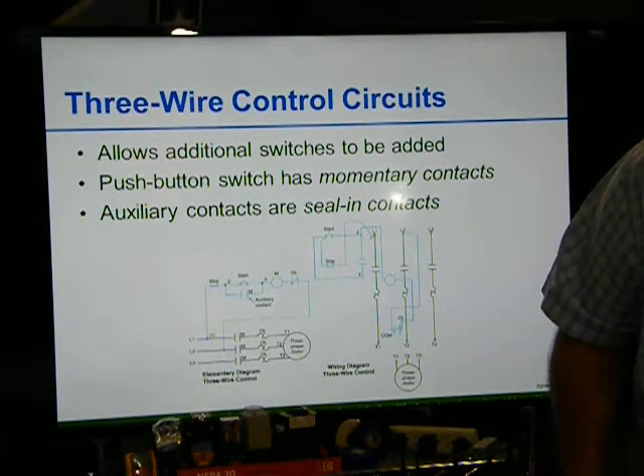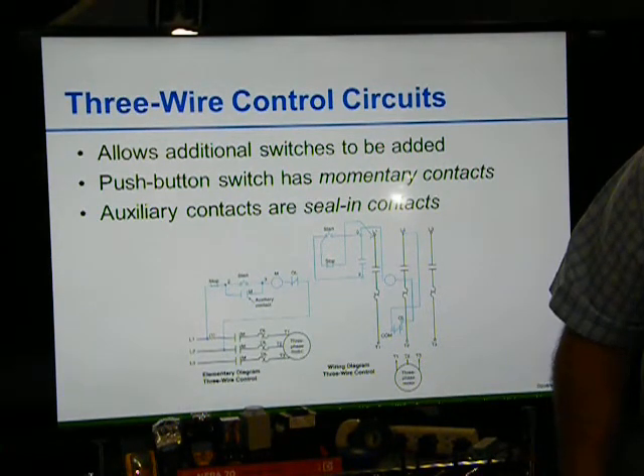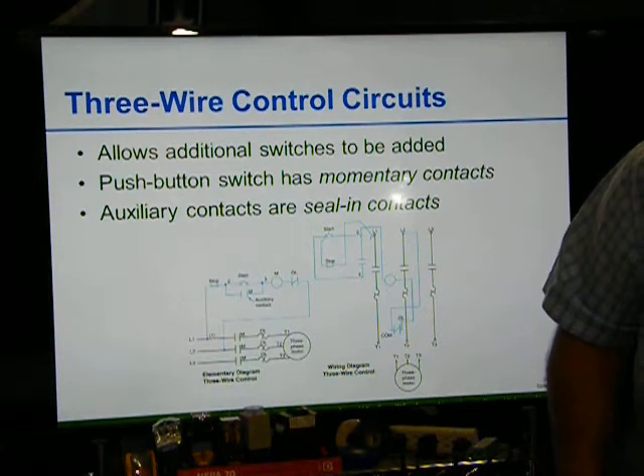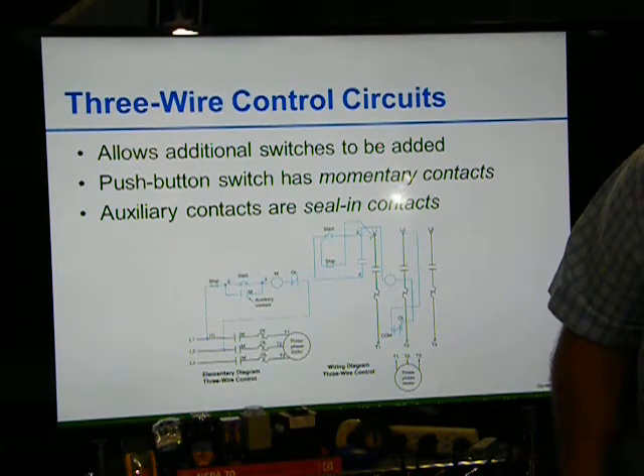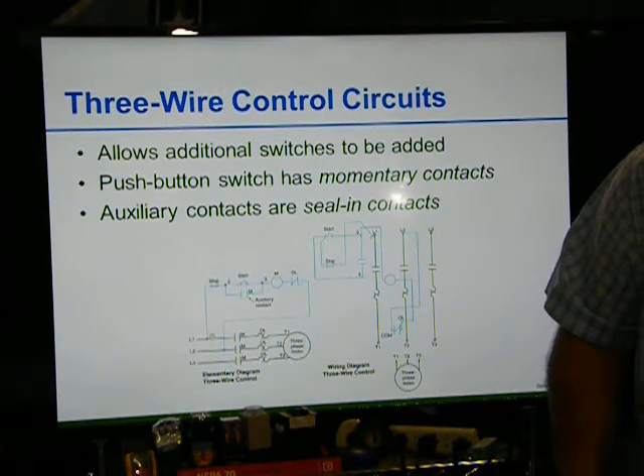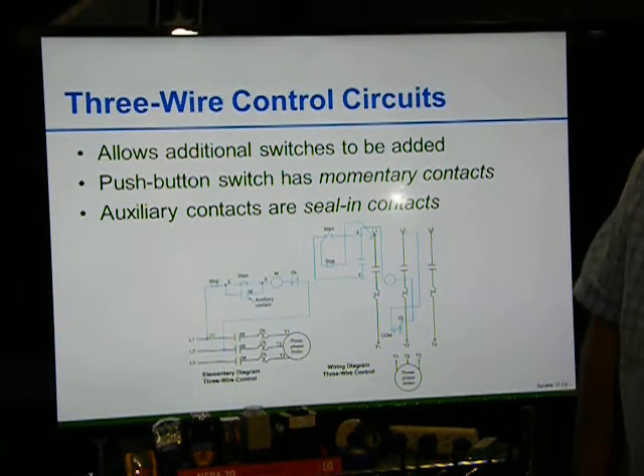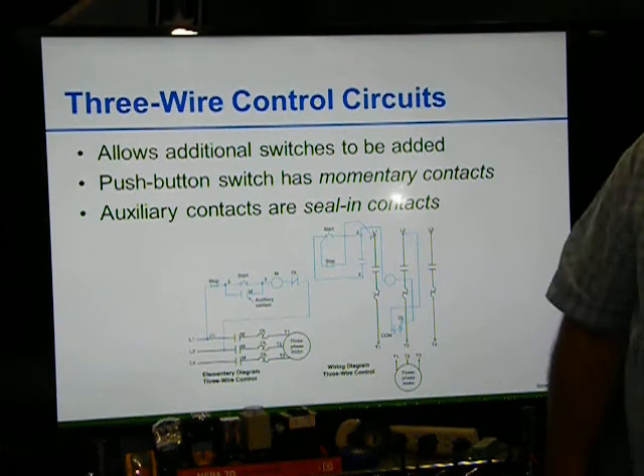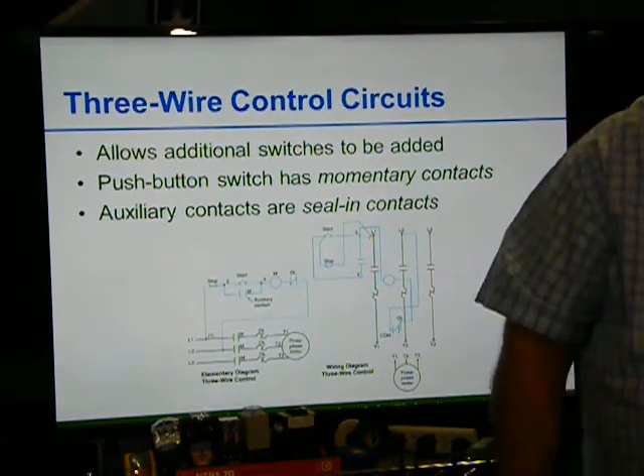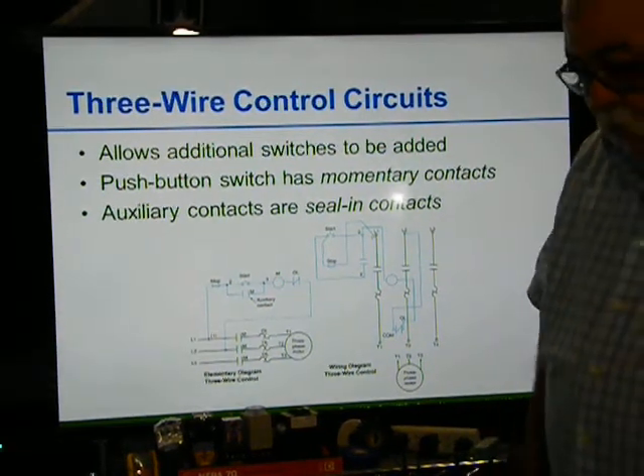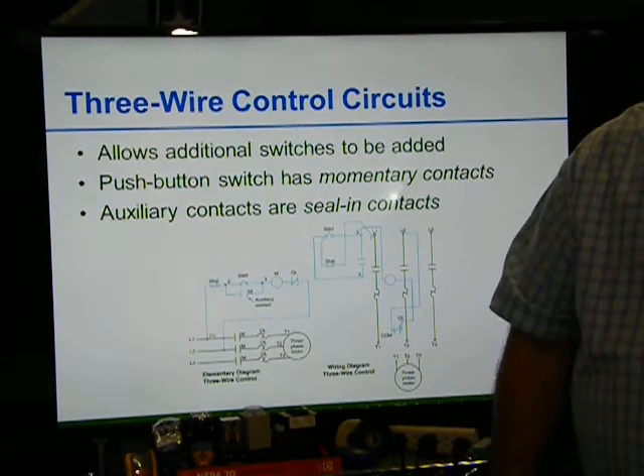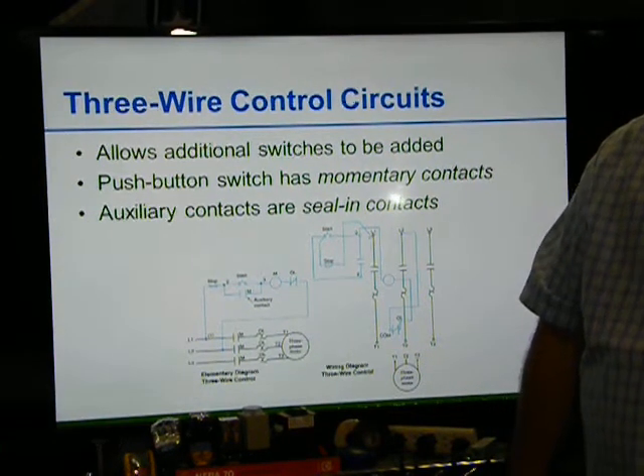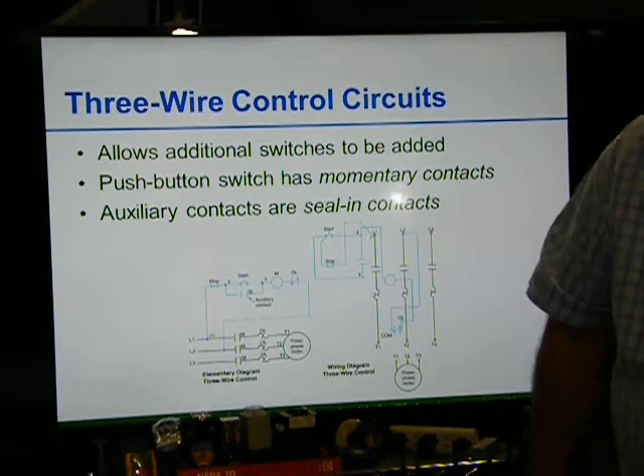It says a few cycles of low voltage will cause the starter contact to open and stop the motor. This prevents a motor from trying to run on low voltage, a major cause of motor failures. So if there's low voltage sensing, it can give you that. Let's say you have a problem somewhere and your voltage drops. This will help also open it up.